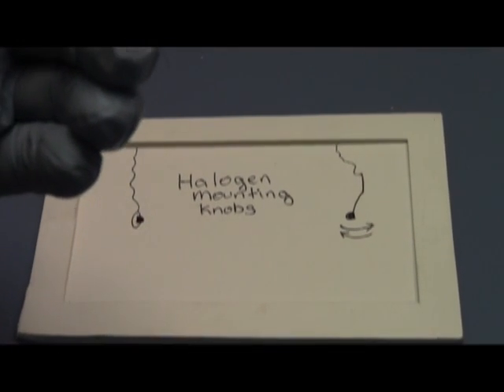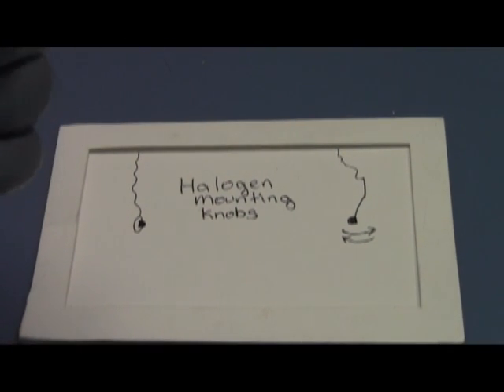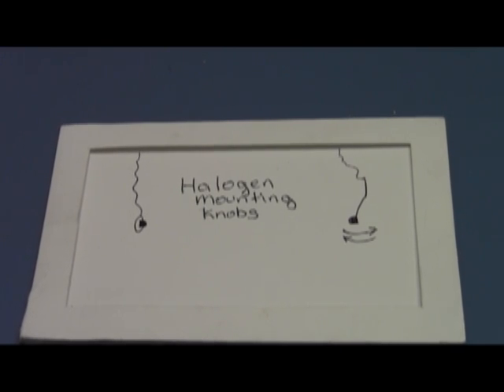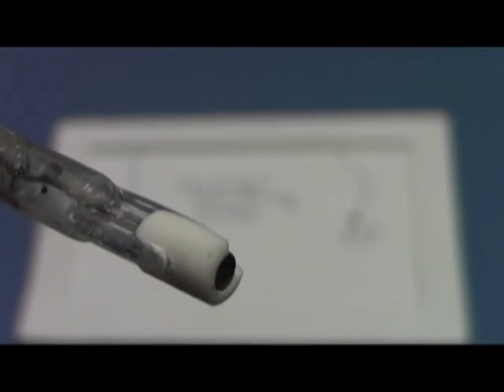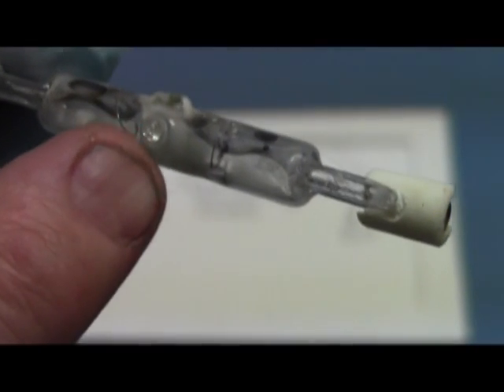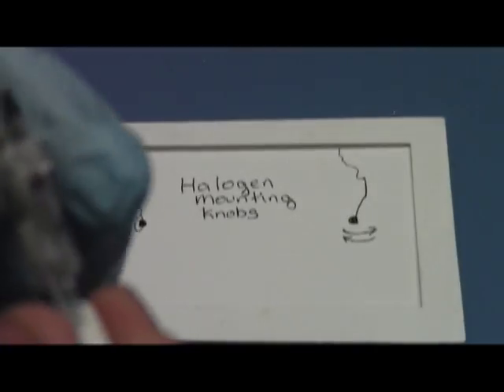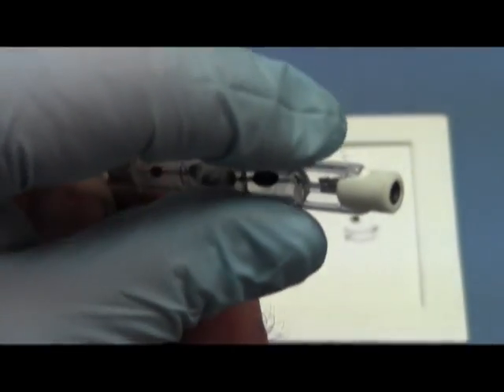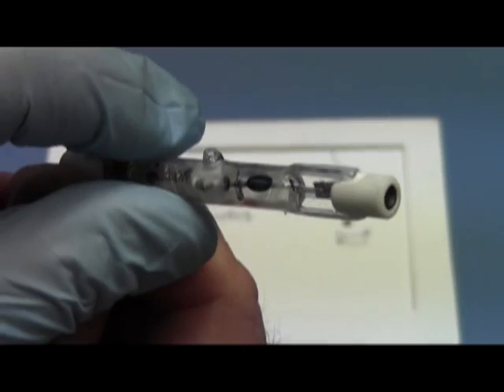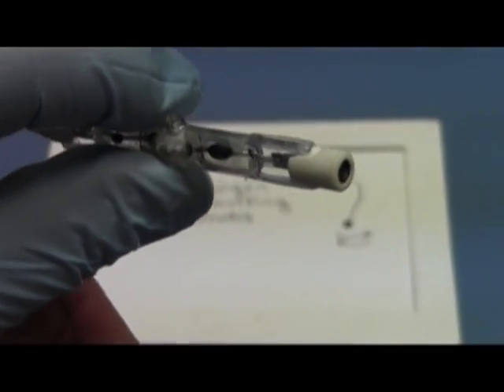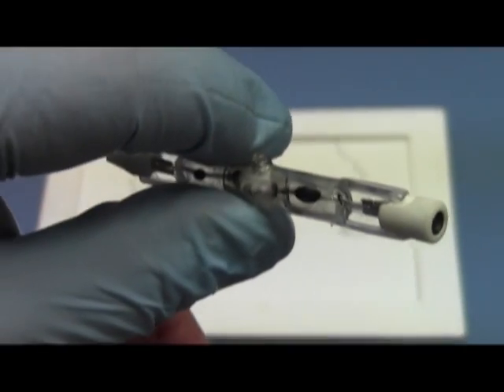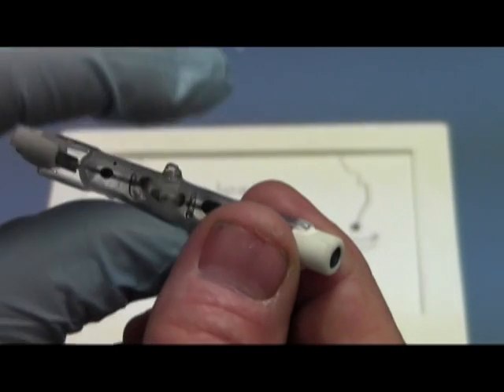Assuming that you're wearing a pair of either nitrile gloves or latex gloves, you're going to have to be very careful when you install them. All halogen bulbs have a little knob here. That knob is so that you have traction on the bulb when you go to install it. The proper way of handling these is to have your finger on either side of the bulb. So, if you're pushing into the spring in this direction, obviously you want it on that side. Or if the spring is on the other direction, you have it on this side.